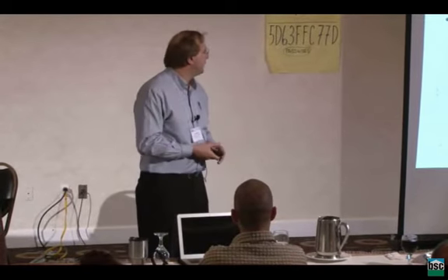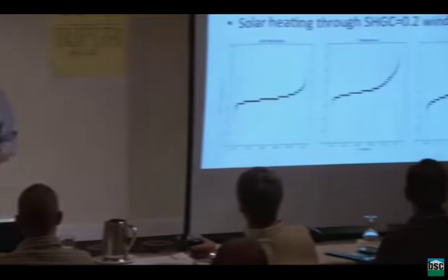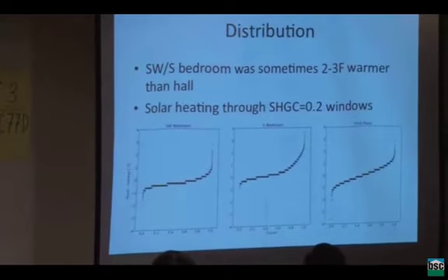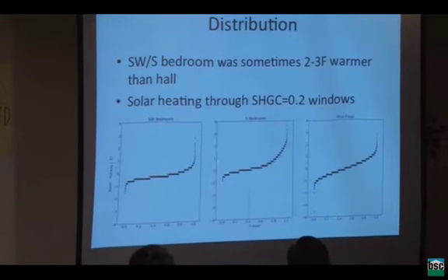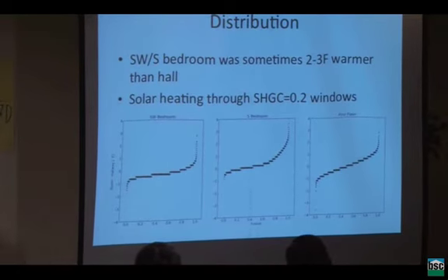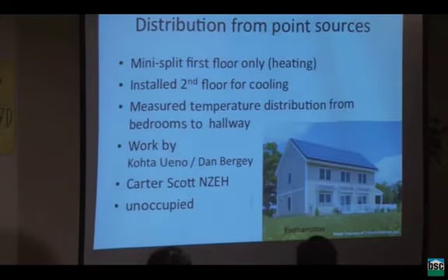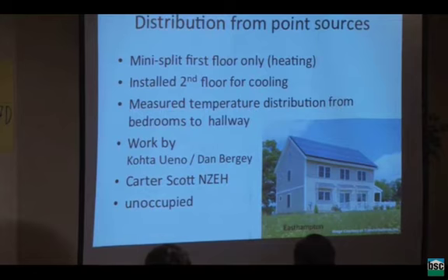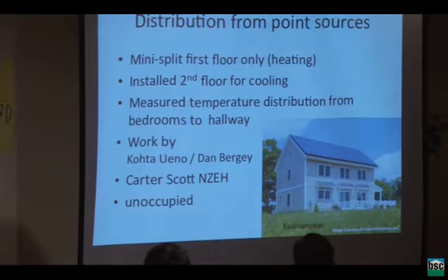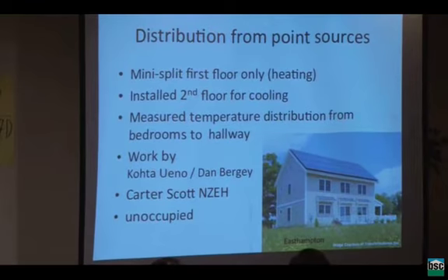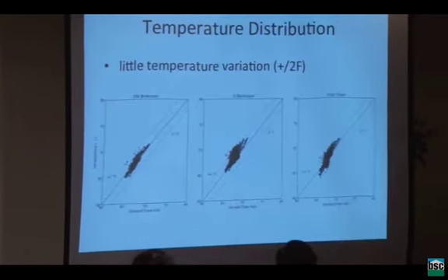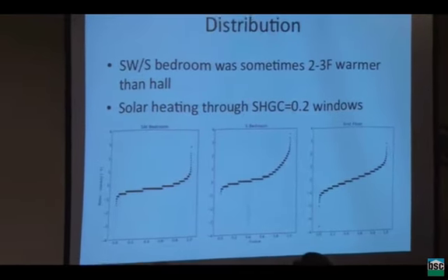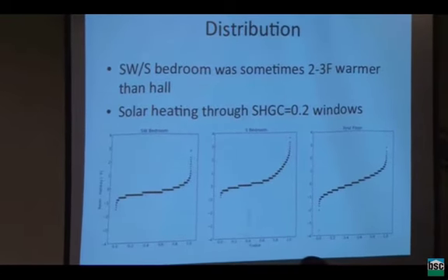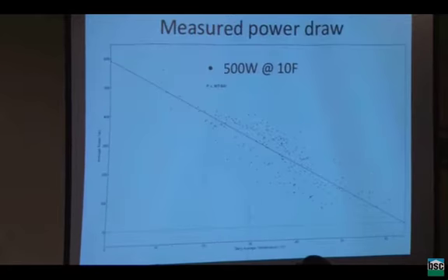Sometimes, this is now a probability distribution, there were a few hours, but not many, where we're as much as 3 degrees warmer. And actually, when that was tracked back and correlated with weather conditions, that was the southwest and south bedrooms when it was sunny and the solar heat gained through the windows. Now you'll notice, this is not a house that's known for excess of windows, right? It's quite modest, and they're triple glazed, low solar heat gain. And yet the temperature excursions are still driven by the solar gain. Now you start getting bigger windows, aiming for high solar heat gain, and this is not going to work. There's no way that'll work with a central system, like a central hallway mounted thing.